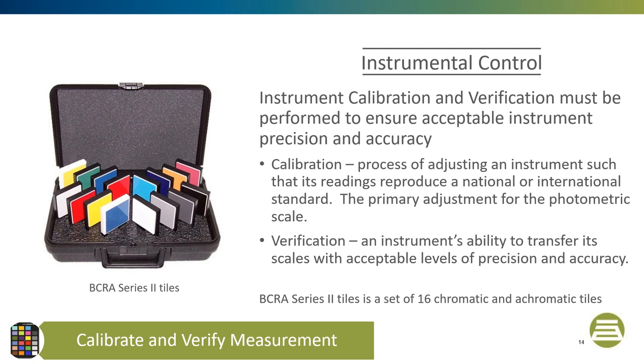Verification, on the other hand, is not enforced. Spectrophotometer verification is done by measuring a set of certified colored tiles with known reflectance measurements. These measurements are compared to your spectrophotometer's measurements. Verification of your spectrophotometer can help reduce the cost of measurement drift, identifies instruments in need of service, and helps to avoid inaccurate color production of products.